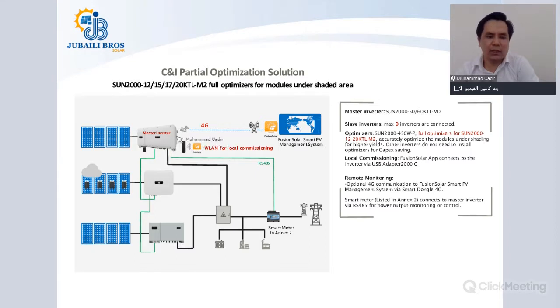Alternatively, you can have a 12 to 20 kilowatt size inverter as a slave, and the master inverter in this scenario can be 36 kilowatt or 100 kilowatt, or even 50 and 60 kilowatt. Here, since you are using the dongle, you will be connecting a maximum of 9 slave inverters, and one of the slave inverters would be 12 to 20 kilowatt size, on which you will be doing full optimization, while the rest of the inverters will not have power optimizers.